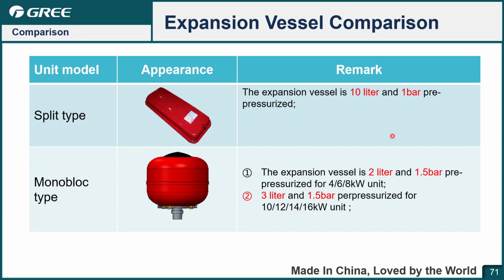That's the structure difference. Another difference is the expansion vessel. For the split type, it's flat, and the volume is 10 liters with 1 bar pressure preset. For the monoblock, it's a cylinder. The expansion vessel is 2 liters and 1.5 bar for this 3 model, and 3 liters and 1.5 bar for this 4 model. Because the space in the monoblock units is very narrow, we cannot use the flat type, so we changed to the cylinder type and integrated it into the unit. But the function of these two types is the same.